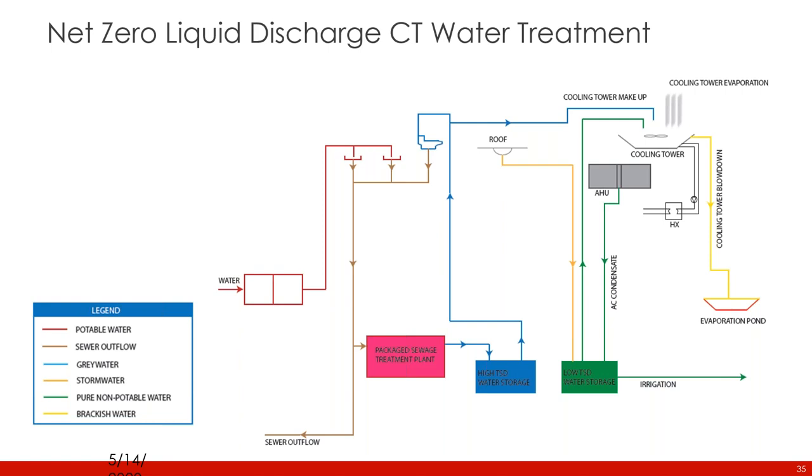And as a result, there are huge amounts of cooling tower blowdown flowing into the local sewer system. So remember, we're controlling our cooling towers to have a total dissolved solids level of 1500 to 2000 parts per million. So when you've got a multi-megawatt power plant, that's a huge amount of blowdown flowing into the local sewer system.